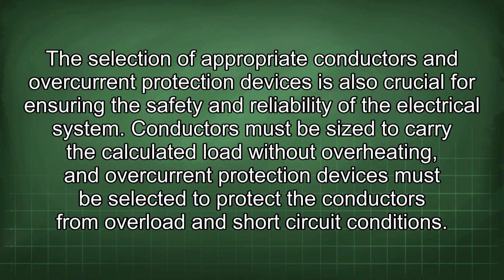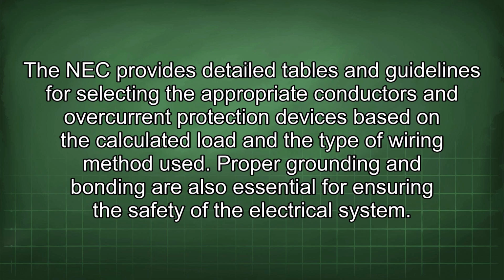The selection of appropriate conductors and overcurrent protection devices is also crucial for ensuring the safety and reliability of the electrical system. Conductors must be sized to carry the calculated load without overheating, and overcurrent protection devices must be selected to protect the conductors from overload and short-circuit conditions. The NEC provides detailed tables and guidelines for selecting the appropriate conductors and overcurrent protection devices based on the calculated load and the type of wiring method used.